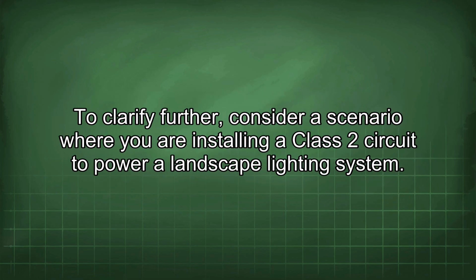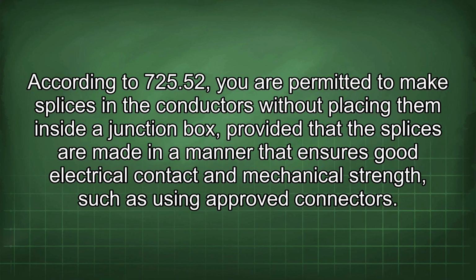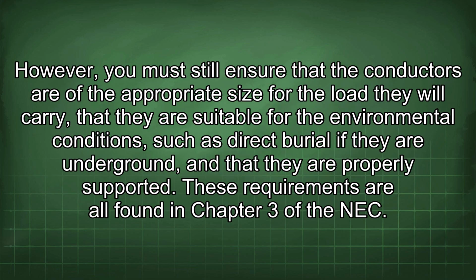To clarify further, consider a scenario where you are installing a Class 2 circuit to power a landscape lighting system. According to 725.52, you are permitted to make splices in the conductors without placing them inside a junction box, provided that the splices are made in a manner that ensures good electrical contact and mechanical strength, such as using approved connectors. However, you must still ensure that the conductors are of the appropriate size for the load they will carry, that they are suitable for the environmental conditions, such as direct burial if they are underground, and that they are properly supported. These requirements are all found in Chapter 3 of the NEC.